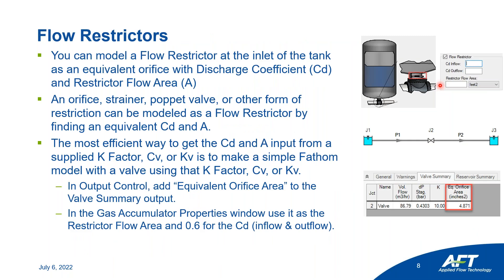Any passive restriction at the inlet of the gas accumulator tank can be modeled as a flow restrictor. The flow restrictor is assumed to be an orifice with a CD and area value. However, you can model a strainer, valve, or any other form of restriction by using an equivalent CD and area value. The most efficient way to get that CD and area input from a supplied K-factor, CV, or KV is to make a simple Fathom model with a valve using that K-factor, CV, or KV, then in output control add the equivalent orifice area parameter to the valve summary output. Once you get that value from Fathom, you can go back to the gas accumulator properties window and use it as the restrictor flow area.